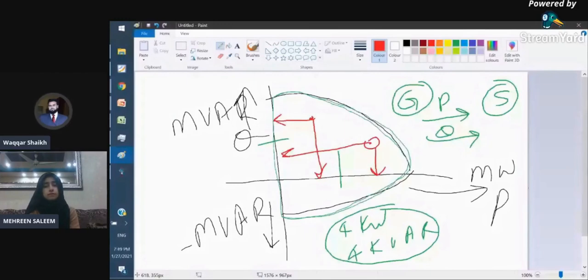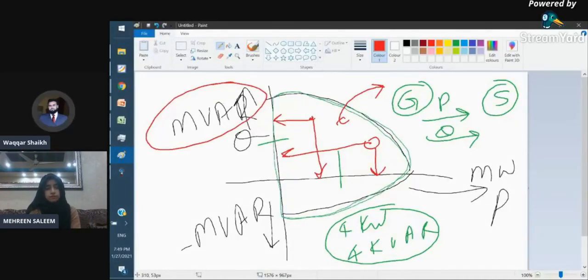Whenever this point goes out of this range, what does it mean? The generator is providing more reactive power, the Q power, to the network. It will jump through this reactive capability limit, which is dangerous for the generator and will damage it. So we never let this situation come. Before reaching this situation, the protections inside the generator will come on to safeguard it, and will shut the generator, cut off the load, or do some load shedding.